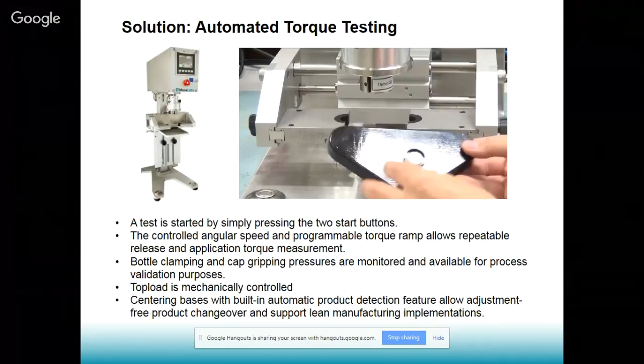So this is also helping with world-class manufacturing implementations, because the more you can minimize the operator's involvement on how to change the recipe, the more likely that your setup and your testing will be repeatable. And as far as the ergonomic improvement, it's obvious that you can just start the test by pressing push buttons instead of manually clamping the bottle and manually doing anything. The automated rotation takes away the repeatability issues too. Top load is mechanically controlled and repeatable, and the bottle and cap gripping pressures can be monitored and documented as well.